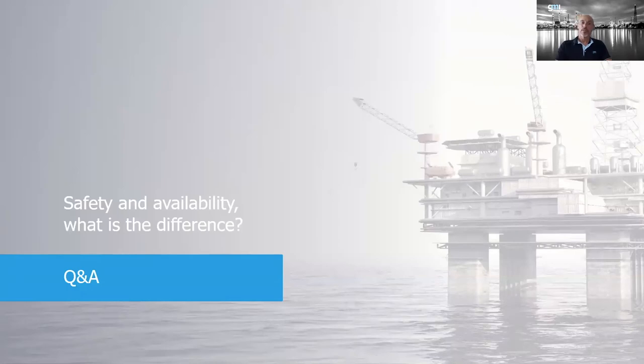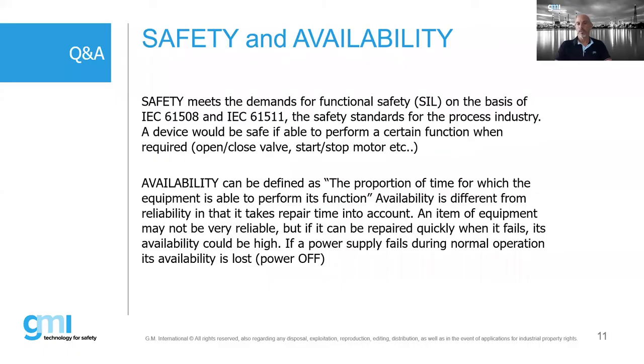Safety and availability, what is the difference? That is very, very important because IEC 61511 is a norm that takes into account just safety and not availability. So safety is the most important parameter. Your plant must be safe, first of all. A device is safe if it is able to perform a certain function. If you have a valve or an actuator, that function may be critical and must be performed with a very high probability. Opening or closing a valve and starting or stopping a motor are the most common applications.